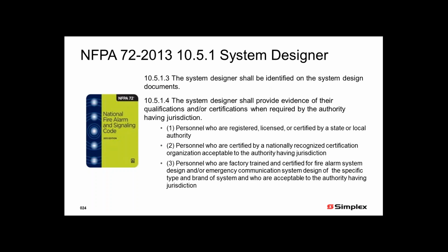Further, we can request the designer to provide evidence. How are you qualified to do this system? What credentials do you have? So we listed a few things here that could comply. Number one, and it's not all of these, it's any one of these. So they're not all inclusive, any one of these would suffice to meet the requirements. So number one, personnel who are registered, licensed, or certified by the state, the country, the local authority, civil defense or what have you.